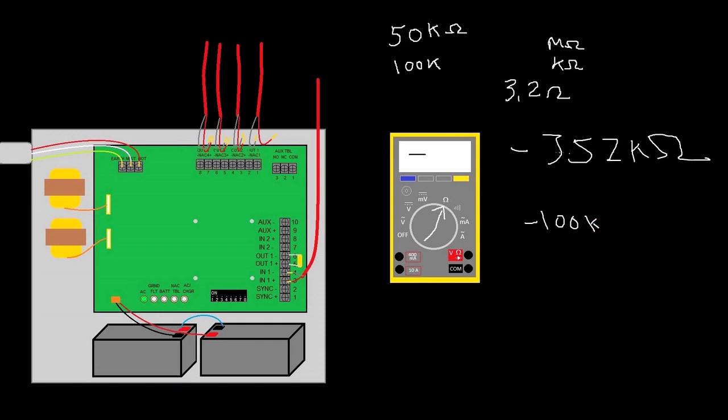To me, the first thing in my mind goes to is I've got a wet module or something on the other side of my module, like a monitor module that's wet. So maybe a valve tamper is leaky and the contacts got corroded or something.